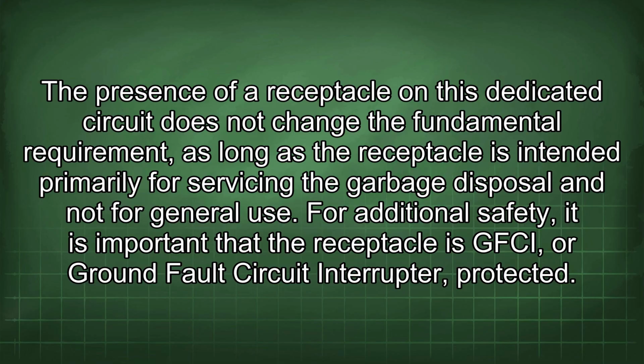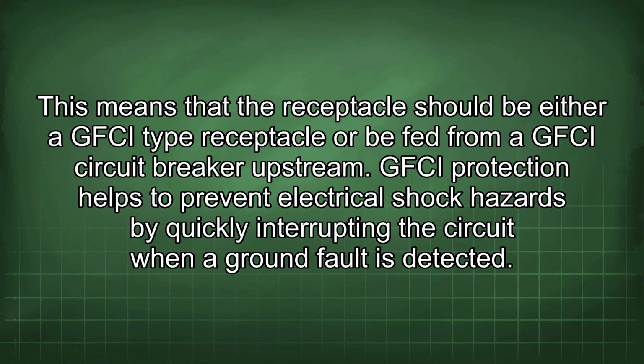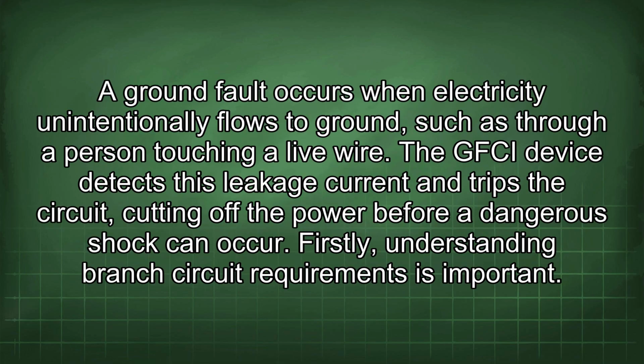For additional safety, it is important that the receptacle is GFCI, or ground fault circuit interrupter, protected. This means that the receptacle should be either a GFCI type receptacle or be fed from a GFCI circuit breaker upstream. GFCI protection helps to prevent electrical shock hazards by quickly interrupting the circuit when a ground fault is detected. A ground fault occurs when electricity unintentionally flows to ground, such as through a person touching a live wire. The GFCI device detects this leakage current and trips the circuit, cutting off the power before a dangerous shock can occur.